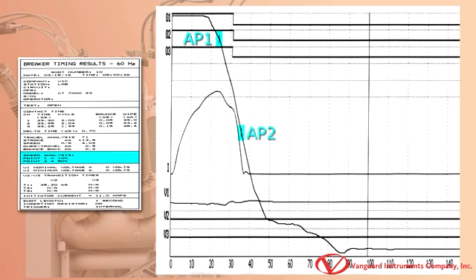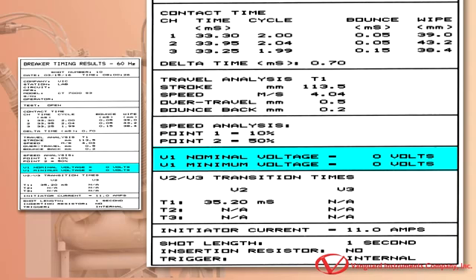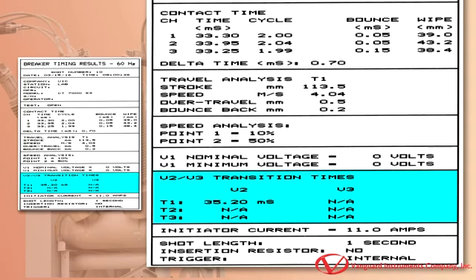The AP1 in this case is the distance that is 10% of the stroke and is measured from the fully closed position. The AP2 in this case is the distance that is 50% of the stroke and measured from the fully closed position. The V1 voltage measurement is shown here. The CT7000S3 will detect the on-off voltage transition on the V2 and V3 voltage input channels. It can detect up to 3 voltage on-off events and record the times. In this example, the CT7000S3 detected 1 voltage transition on the V2 channel at 35.2 milliseconds.